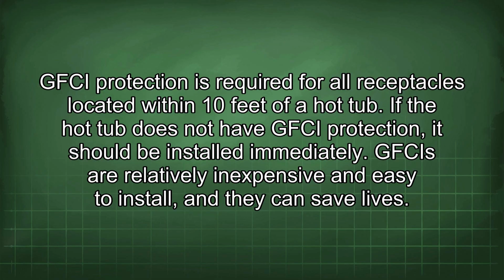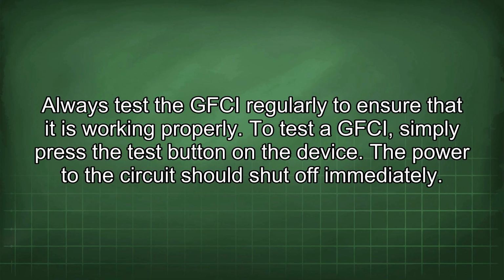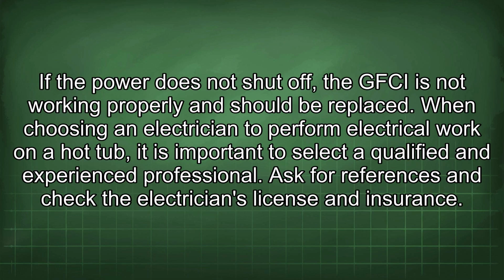If the hot tub does not have GFCI protection, it should be installed immediately. GFCIs are relatively inexpensive and easy to install, and they can save lives. Always test the GFCI regularly to ensure that it is working properly. To test a GFCI, simply press the test button on the device. The power to the circuit should shut off immediately. If the power does not shut off, the GFCI is not working properly and should be replaced.